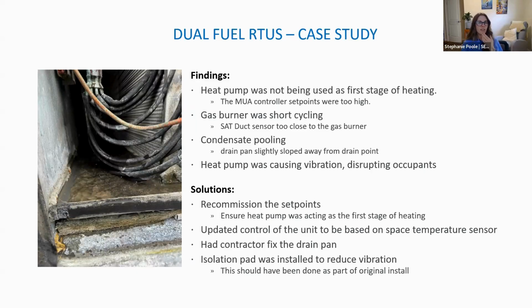There were some other things with the install that weren't proper. There was vibration. They should have had a vibration isolation pad on there, which should have been done as part of construction. It wasn't, so the occupants were hearing this vibration. It was very disruptive, and they were not feeling very good about this retrofit. And then there was some condensate pooling. That's what that picture is. Again, the condensate drain is one of the things we see very often in all heat pump installs. The condensate is a big issue, and if it's not installed correctly, you can get freezing or pooling, or it can make a mess.